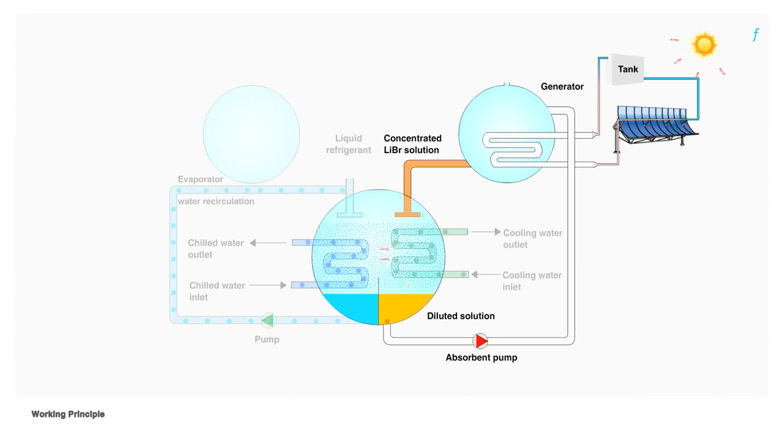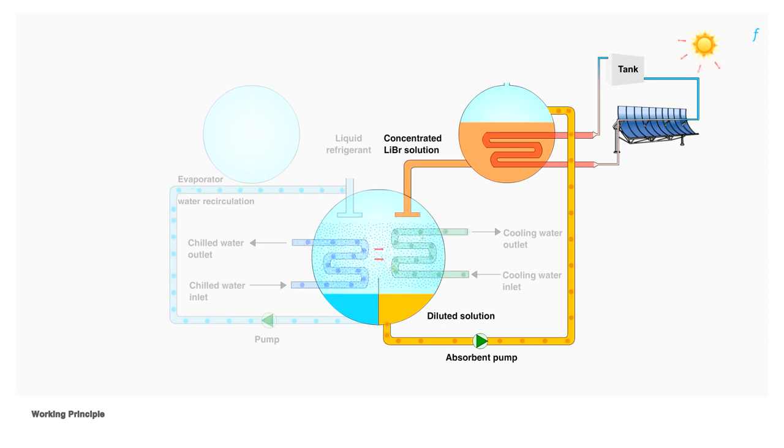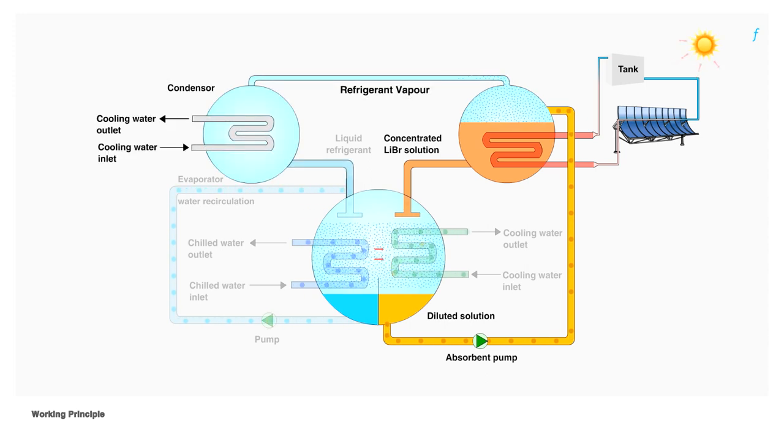The next element in this cycle is the generator. The diluted lithium bromide solution is pumped up to the generator for re-concentration. Here, an external heat source, that is heat from the solar collectors, is used to heat up the solution. The heating process vaporizes water from the solution, thereby increasing the concentration of lithium bromide. The re-concentrated lithium bromide solution is directed to enter the absorber unit, forming a cycle of its own.